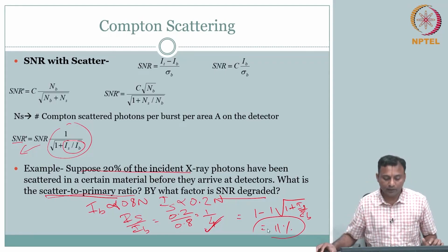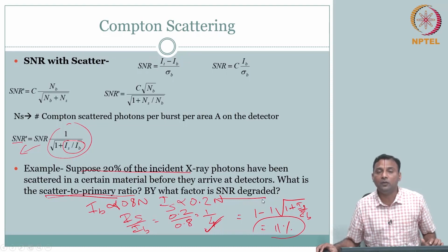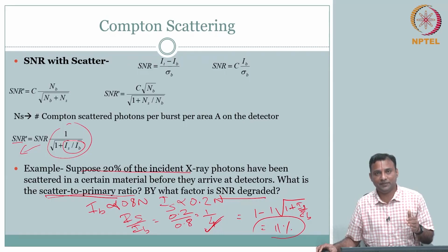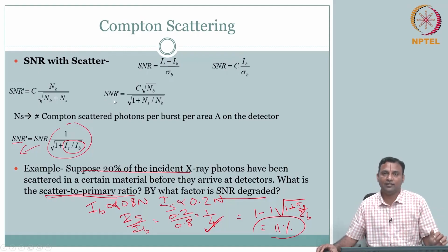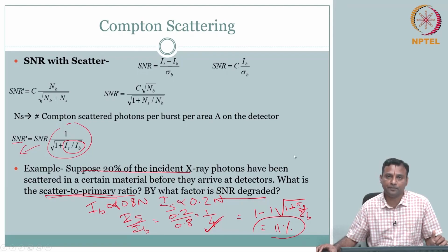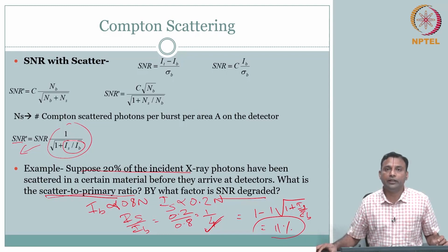So, this is a very important aspect, because image quality, what we did is, we are able to see most of it is related to the number of photons and the inherent contrast. And then we talked about detector efficiency. So, even after you have a particular detector, if you can manipulate N, you can manipulate your signal to noise ratio. Whichever form we saw, with scattering, without scattering, noise by itself, this N, number of photons, plays an important part. Okay. So much for noise and scattering, which is to do with your image quality.